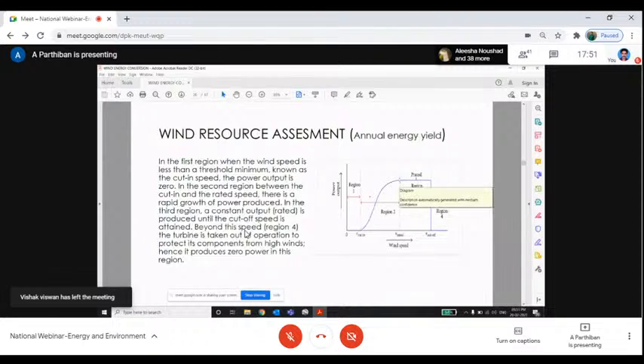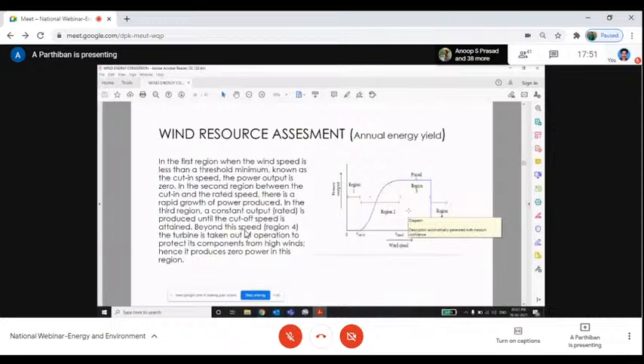Region 3 is the rated speed. At a particular wind speed, the turbine will attain the full power generation, 2 megawatt. For example, at 12 meter per second, 2 megawatt will be the rated capacity. From 12, even if it is 15 or 16 meter per second, the turbine will produce only 2 megawatt. Region 4 is the cut-out wind speed: after a particular wind speed, 20 to 25 meter per second, the wind turbine will stop due to safety reasons.